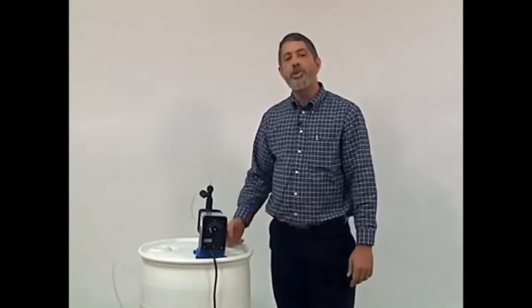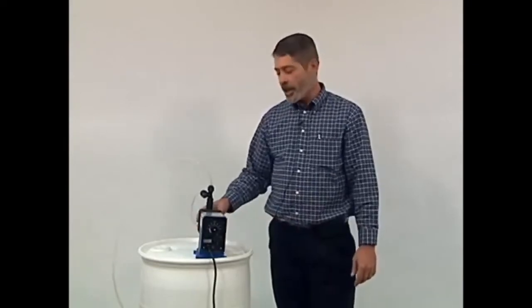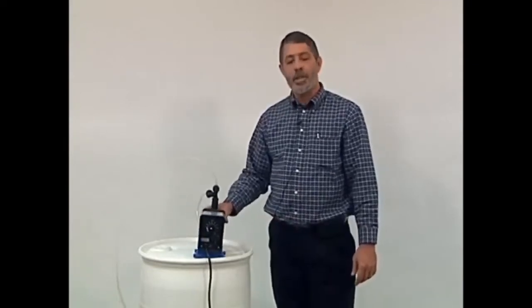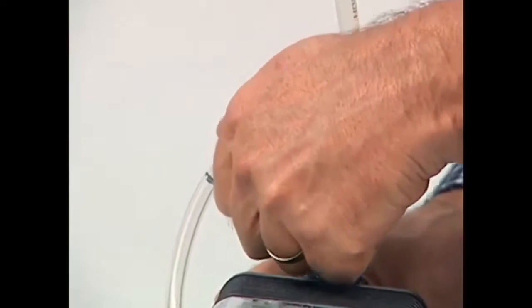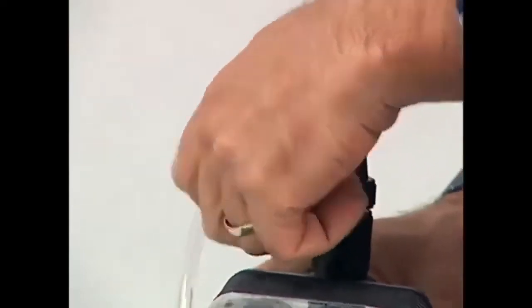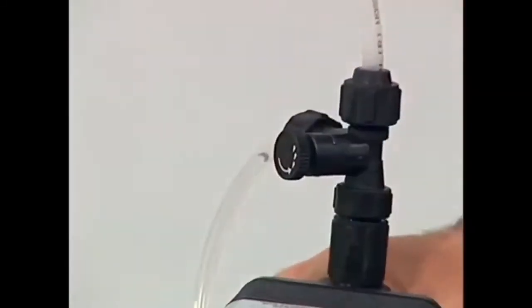There's 2 or 3 things you can do in a situation like that. The first is obviously to use your priming valve, just like you did when the pump was new. Simply open it, run the pump, see if the pump will prime. Occasionally, the priming valve is not enough. We have wear or tear or debris that's made its way in. Some chemicals crystallize. Various things can happen.